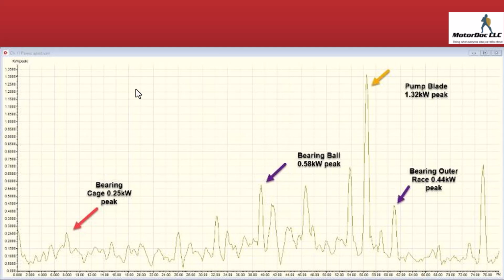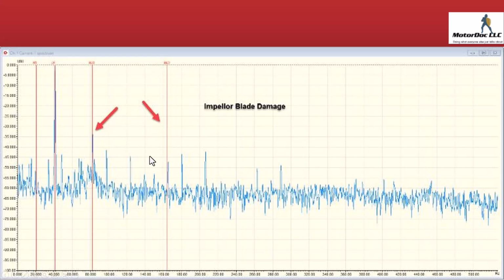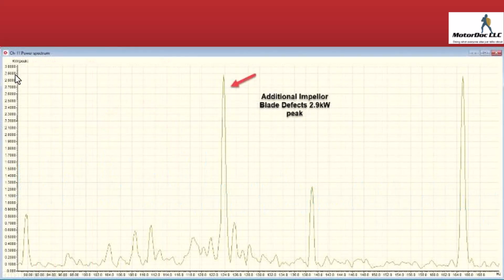And when we started taking a look at a few things, we also discovered, because two of the pump blade frequencies were very, very high, it turns out when this thing was being assembled, because this is a commissioning test, so this machine's only been in place for a little bit, somebody had dropped and dinged one of the blades on the impeller. And that little ding caused problems with turbulence, but also caused an energy loss. Turbulence is a huge energy cost. But if we take a look, the bearing cage, there's the peak there, ball, race, and the pump blade, and then the impeller damage, there's the remaining, and you can see about 2.9 kilowatts.